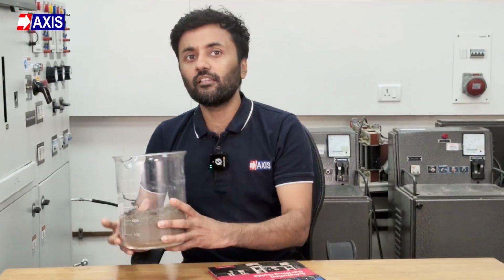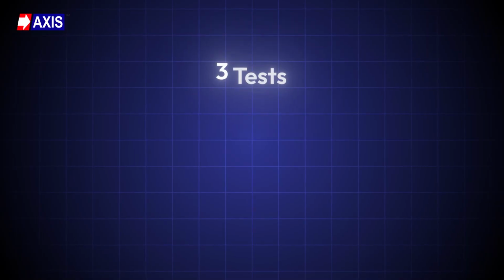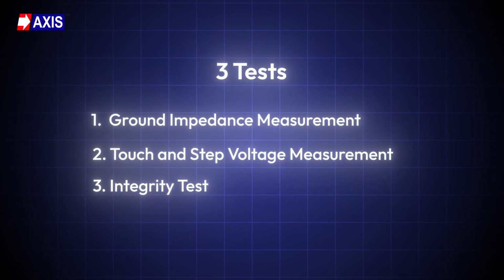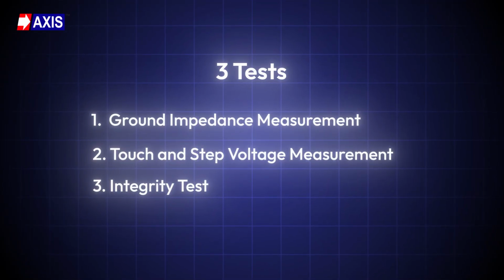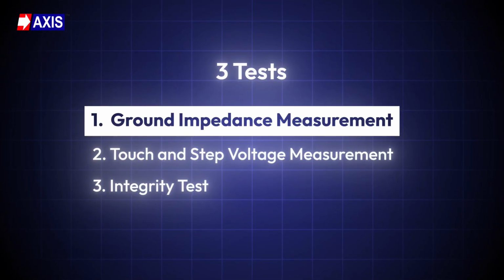These strategies bring the design within safe limits, but once the system is installed in the field, how do you know it is actually performing as designed? I'll give you 3 tests which will help you identify this problem. The first is the ground impedance measurement, which measures the total resistance of the earthing system to remote earth. It gives you a direct estimate of the GPR the system will produce during a fault.